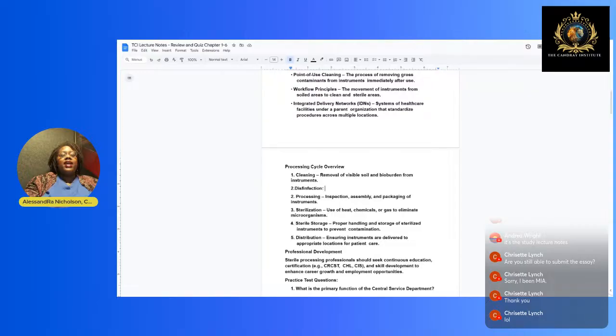And once that sterile package comes out, if it's in a high temp machine, you're going to let it cool down until it's safe to handle and all of the packaging is sealed back up. And if it's a low temp, you're going to go straight from the sterilizer into sterile storage. Sterile storage is where you properly handle and store all of your sterilized instruments to prevent contamination. Remember, this is a room that is temp controlled, and has air exchange delineated for it. Make sure you know what that is.